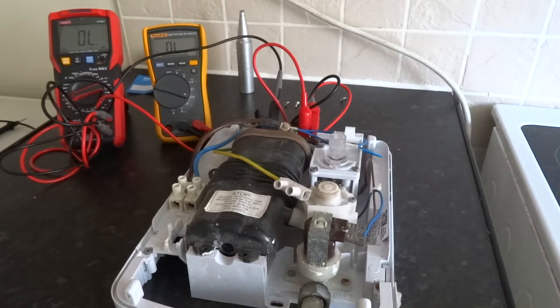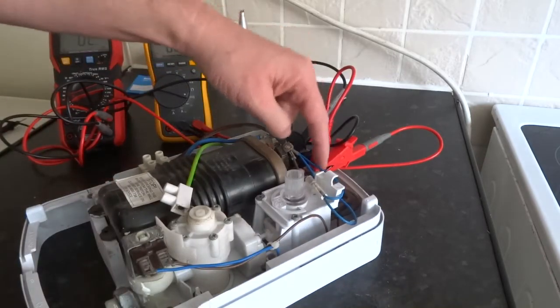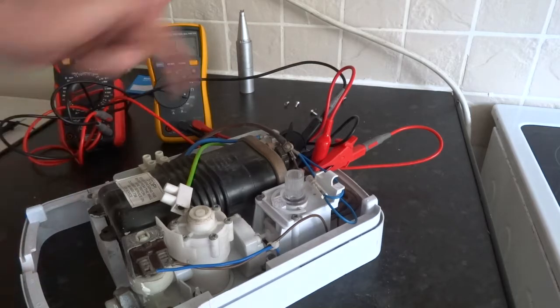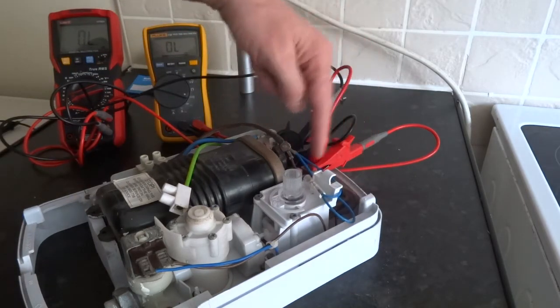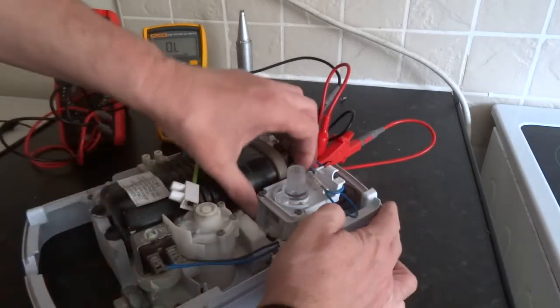I'm going to test all these micro switches. I've got them linked across the inputs and outputs of the micro switches — easy to do. Just on one side of the thermal cutout and then on the outlets to each of the elements. It's in the on position now. When you press it, nothing should happen. So that's your pressure switch.